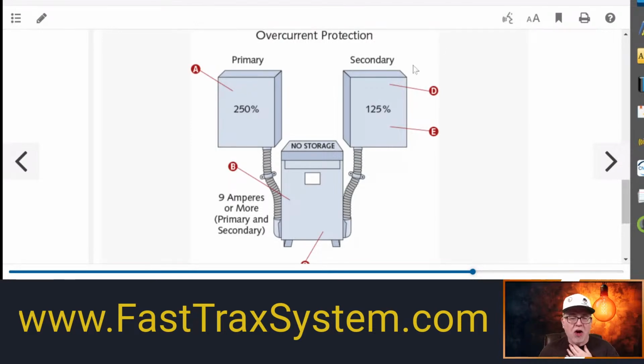Okay. And I also know that if this was 300 amps, because I can, that's a maximum, then these conductors would be sized equal to or greater, because we cannot use the next size up rule. That tells us in 240.21(C) for secondary conductors that we cannot use 240.4(B), the next size up. So they'd have to be full sized right here. Okay.